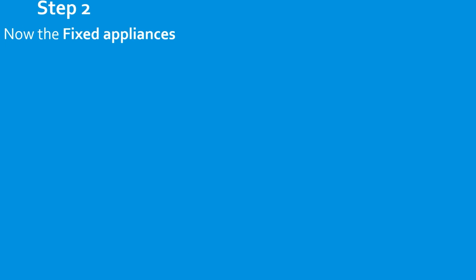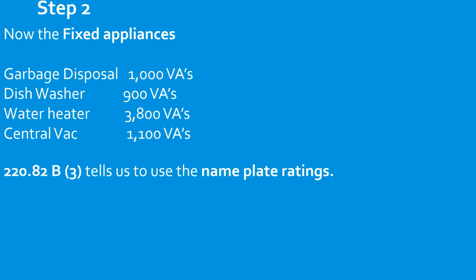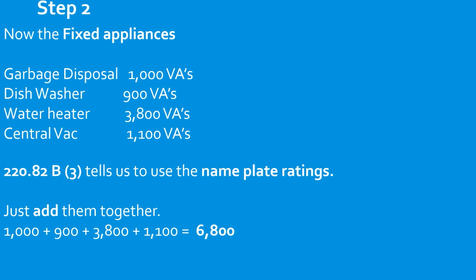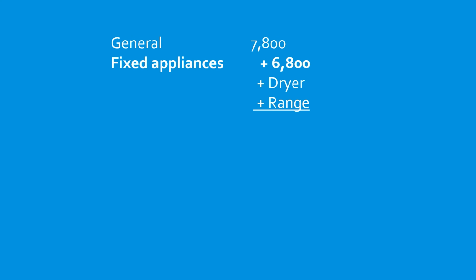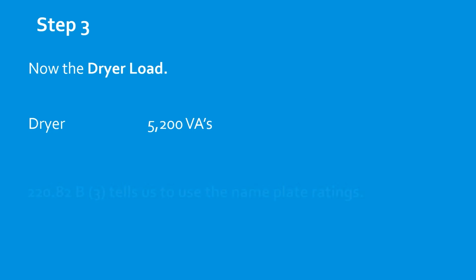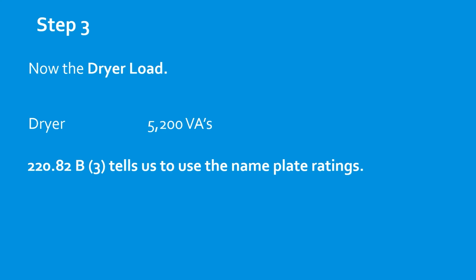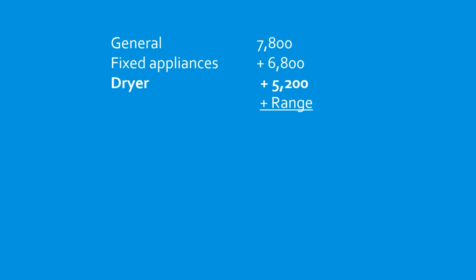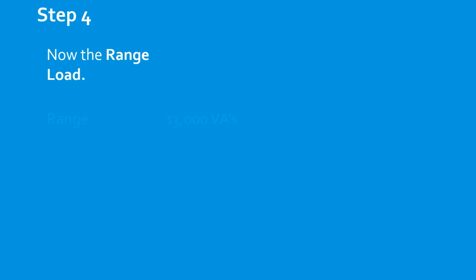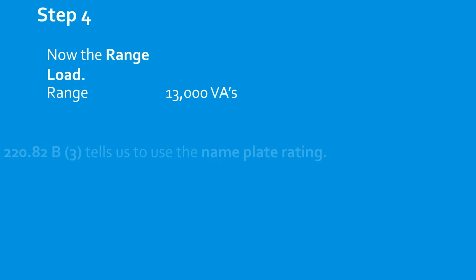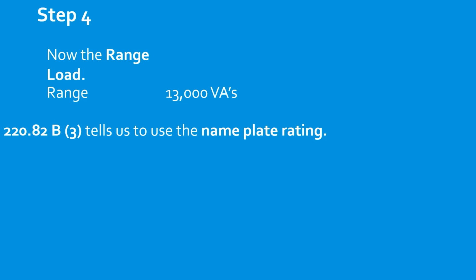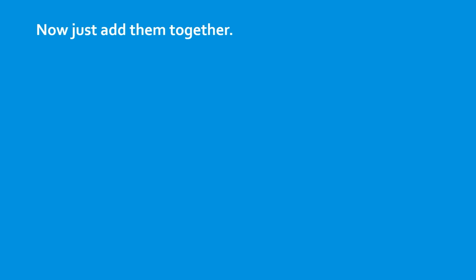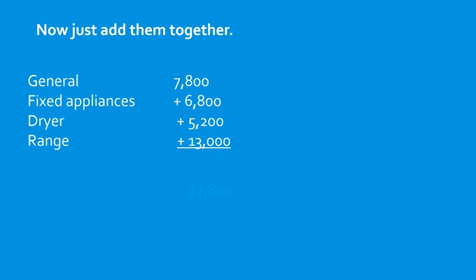Step 2, we're going to do our fixed appliances. In this case, we have more. 220.82(B)(3) states use the nameplate rating, add them together. That's going to give us 6,800 VAs. Now let's calculate the dryer load. 5,200 VAs. We're going to use the nameplate rating when doing the optional method. Step 4, now we're going to do the range load, 13,000 VAs. And we're going to use the nameplate rating. Now we just add them together. That is going to give us 32,800.